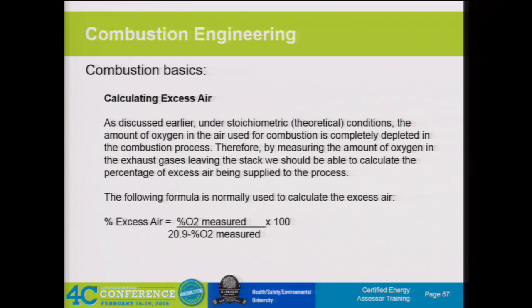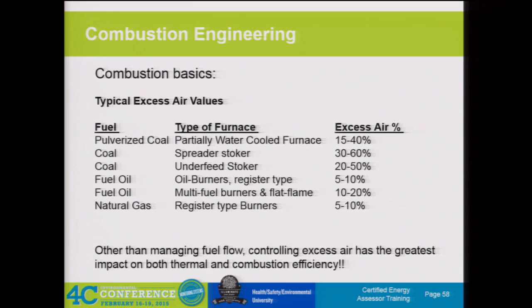The amount of excess air calculation is pretty straightforward. As we measure the amount of O2 in the stack or the exhaust leaving the combustion device, we just take 20.9—being the ambient concentration—minus the amount measured, and with the total amount measured that gives you the percent excess air. That required amount is unit-specific and fuel-specific. Typical examples include pulverized coal at 15 to 40 percent excess air; spreader stoker or other coal systems require a little bit more. As you start to get into the more refined fuels—fuel oil and natural gas—your requirements for excess air drop considerably.